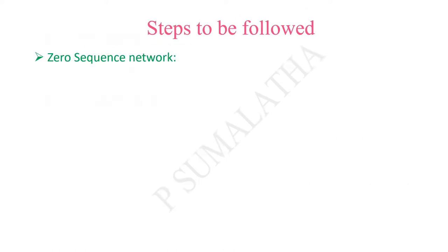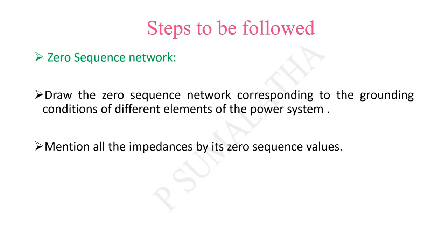Coming to the zero sequence, the zero sequence network is the most important compared to the other networks. Some precautions need to be taken while drawing the zero sequence network because it is represented corresponding to the grounding conditions of different elements of the power system. Especially based on transformer winding connections, we have different connections with respect to series as well as shunt switches — star versus delta — and we represent all impedances with respect to the zero sequence values.